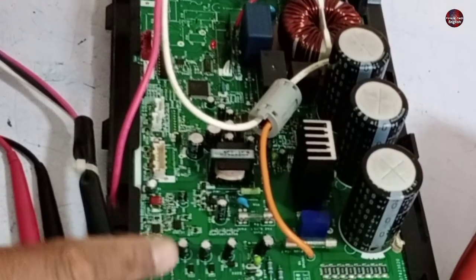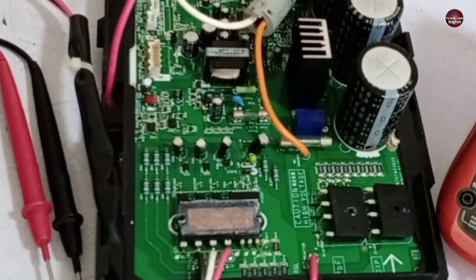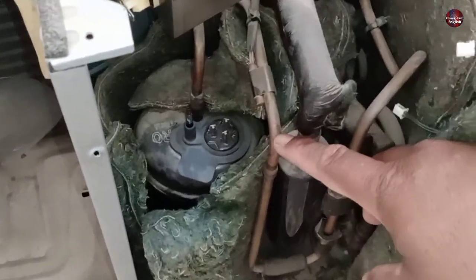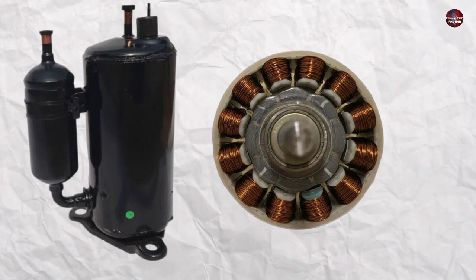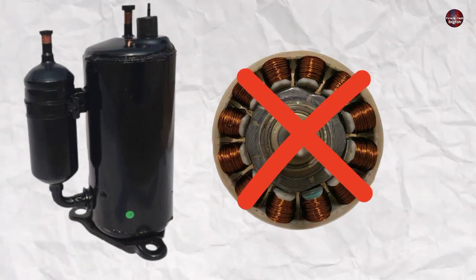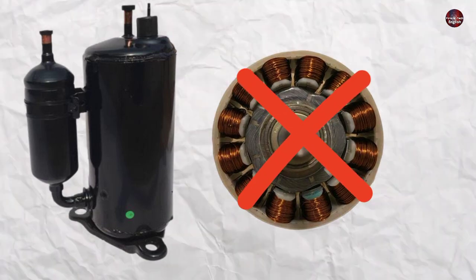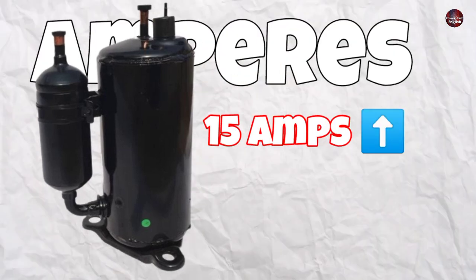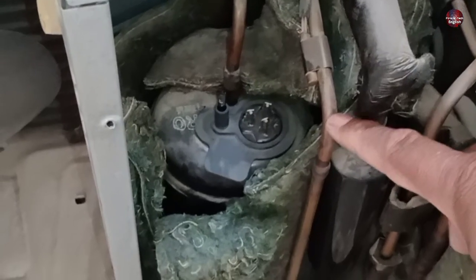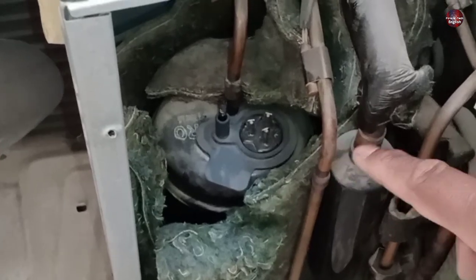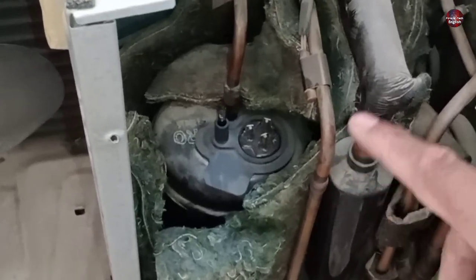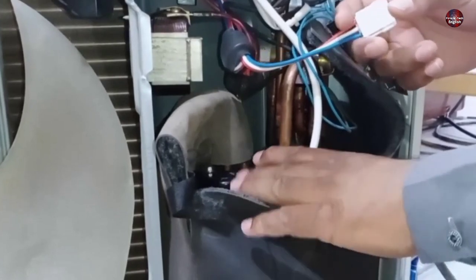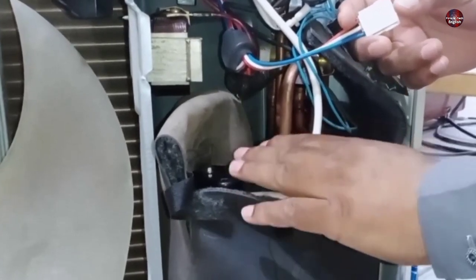Before telling what things to check in the motherboard to fix the current trip error, the first thing you have to check is the compressor of your air conditioner. If the winding of the compressor is short-circuited and it has leakage, the circuit board will detect that the compressor is consuming more ampere than the required amount. The motherboard will trip the compressor and consider this fault as a current trip error. How to test a compressor — I already have a video on it, which will be linked at the end.